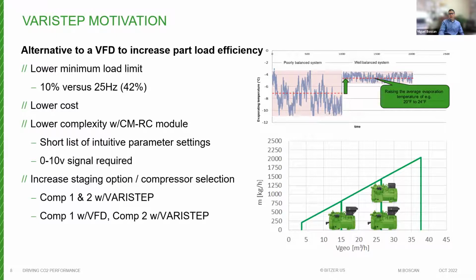requirements of a rack. The VariStep also allows engineers to mix and match VFD compressors with VariStep compressors to achieve the optimal balance between part load, system efficiency, and cost. So in the picture below, we show 2 VariStep options, but you could have a VFD on the first one, a VariStep on the second one, and a standard compressor as well. So they are interchangeable and compatible with each other on a rack. The CMRC simplifies the installation and the controls. You provide the 0 to 10 signal, and the CMRC will do the rest. The goal of it is to improve system efficiency on an overall basis, not compressor efficiency.